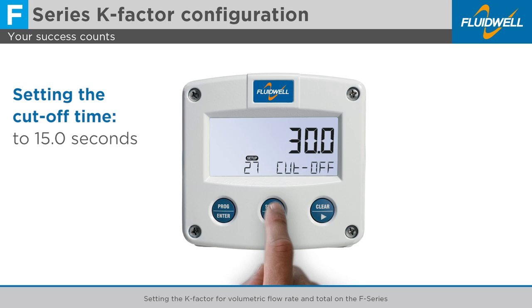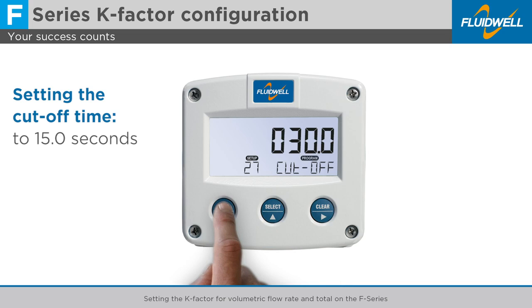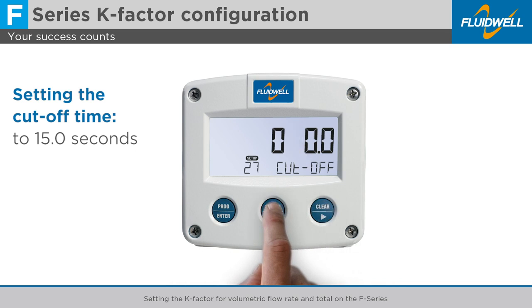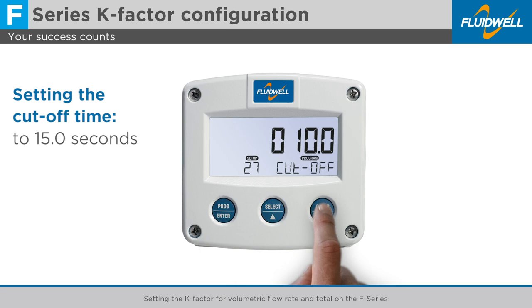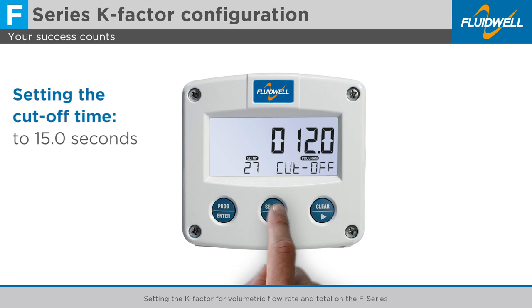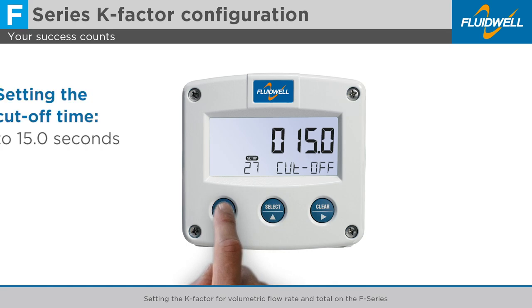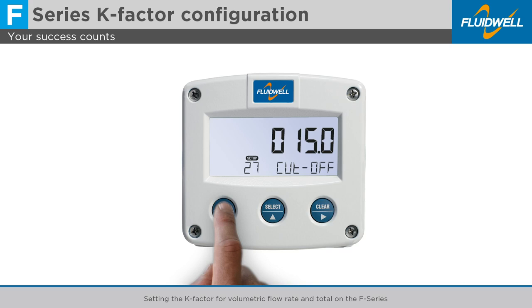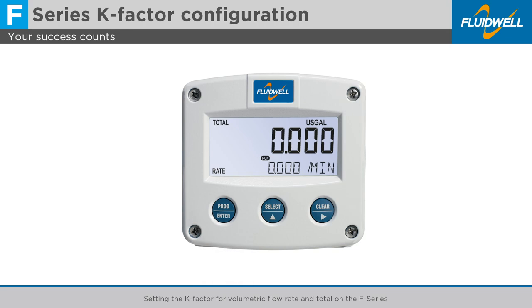Press Select to go to Menu 27, Cutoff. Press Prog to change this setting to a value of 15.0. Press Prog to store this setting. Now all is set, we are going back to Run mode. Hold Prog for 3 seconds to exit the Setup menu and return to Run mode. You can see the configured settings in the main display.